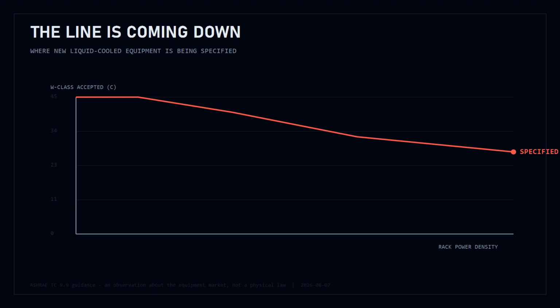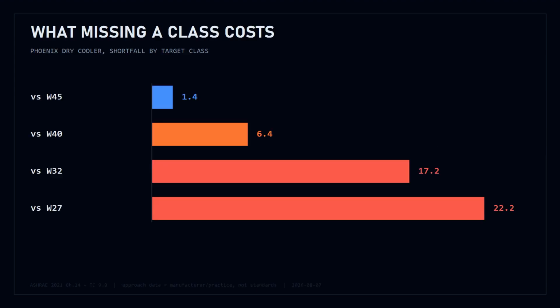But the direction matters. The line you have to clear may be coming down while the heat you are throwing at it goes up. And notice what that does to Phoenix. At W45, its dry cooler is 1.4 degrees short. At W32, it is 17 degrees short. The same city, the same air, a very different problem.